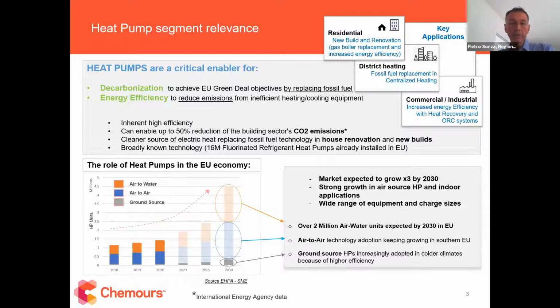The performance of these machines is determined by how much thermal energy can be exchanged with the source, air or ground, versus the electric energy needed to operate the system. This coefficient, called the seasonal coefficient of performance (SCOP), is very high compared to other technologies, very often over 3.5, and in some cases, depending on climate conditions, it can reach higher numbers.